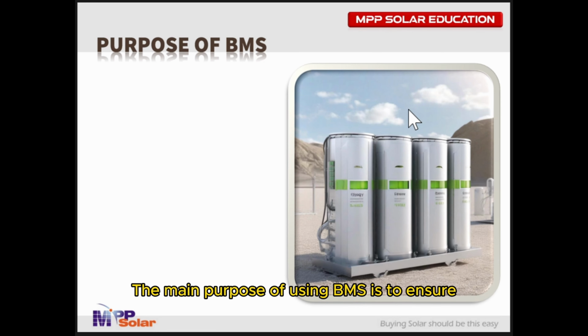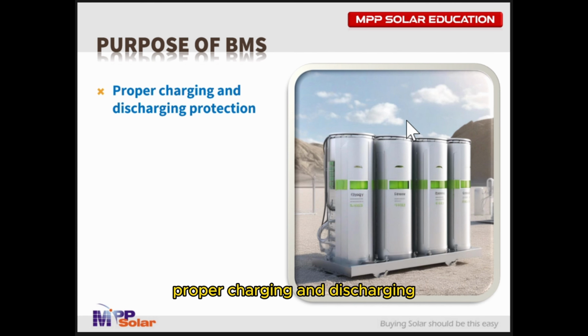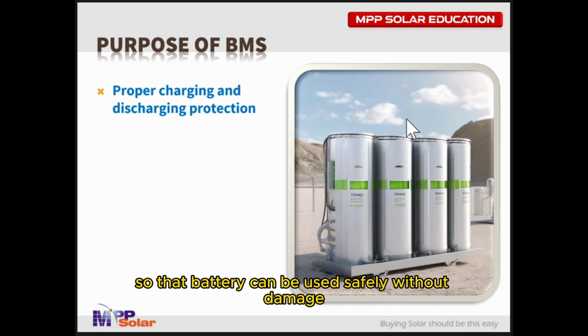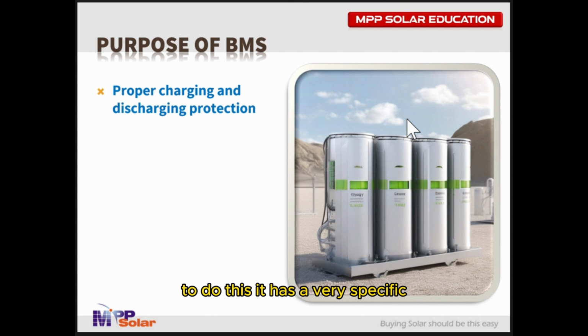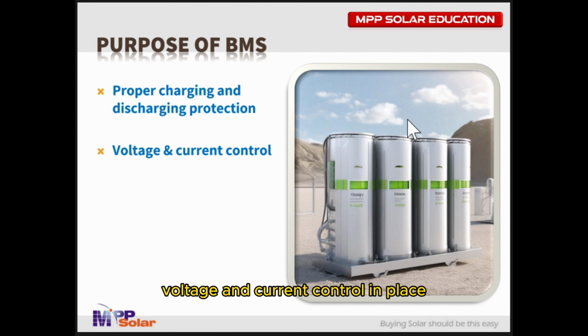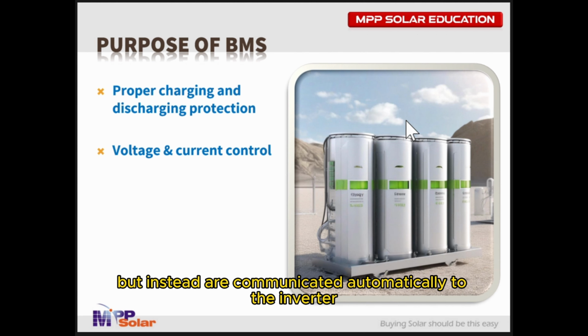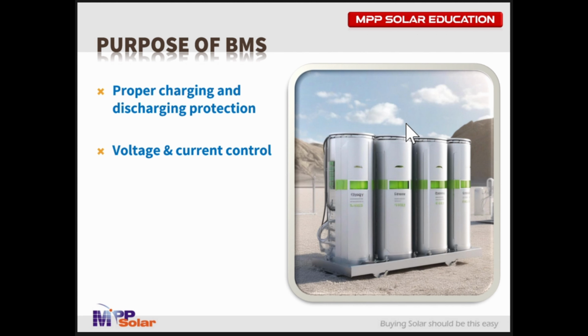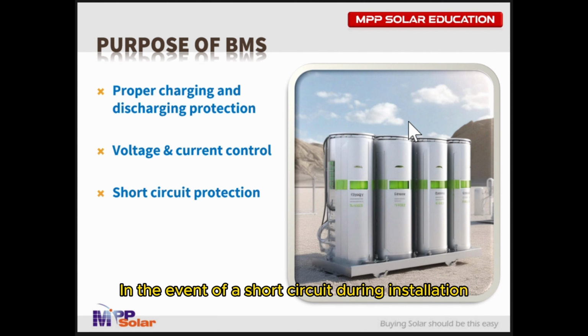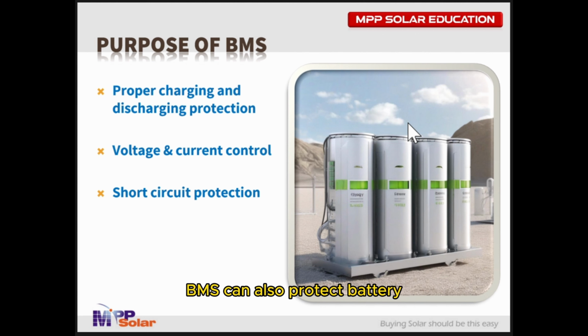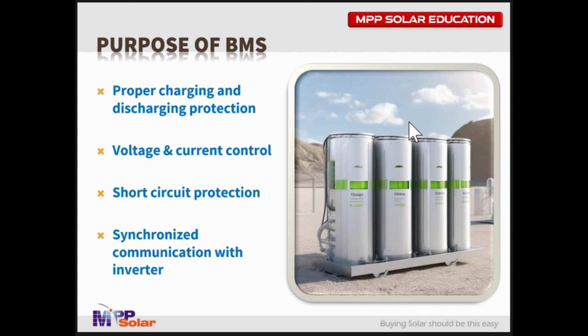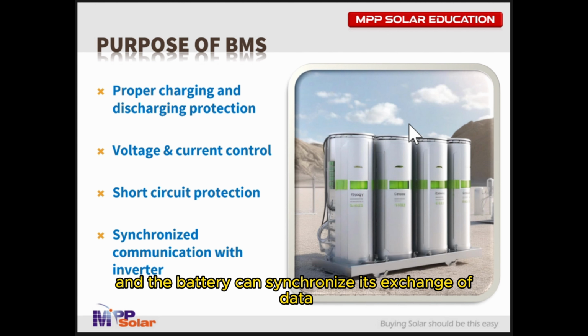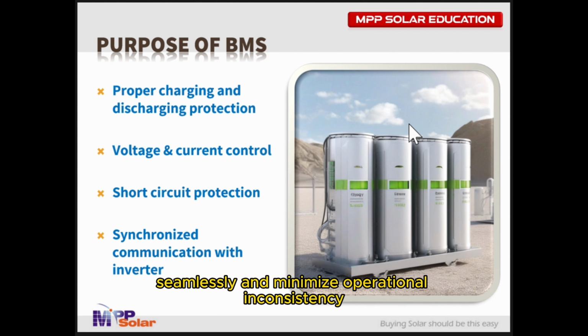The main purpose of using BMS is to ensure proper charging and discharging so that the battery can be used safely without damage. To do this, it has a very specific voltage and current control in place, which is normally not shown to users, but instead is communicated automatically to the inverter once BMS is set up. In the event of a short circuit during installation, BMS can also protect the battery by disengaging itself from the inverter. And last but not least, with a successful BMS communication, both the inverter and the battery can synchronize their exchange of data seamlessly and minimize operational inconsistency.